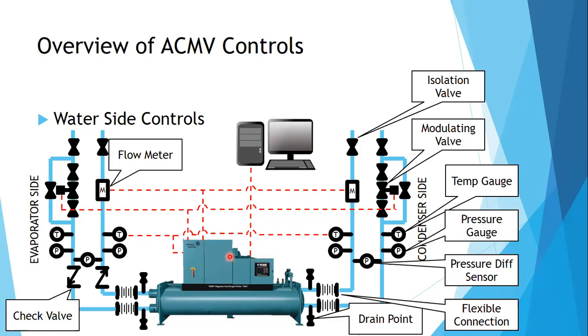So if you go to your chiller units now, you can see your chiller units have their own PLC, have their own display panels, have their own controls. It's not within the BMS. The BMS is there only to extract those data and to see and to monitor. But all these logics are not housed in the BMS, they're housed on your chiller. So the flow meter will go to your chiller PLC, and your chiller will give the appropriate signals to your motorized valve. So your motorized valve will open or will close. Will open 50% or will open 75%.